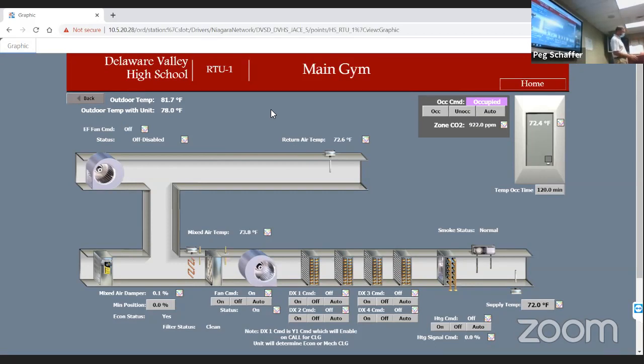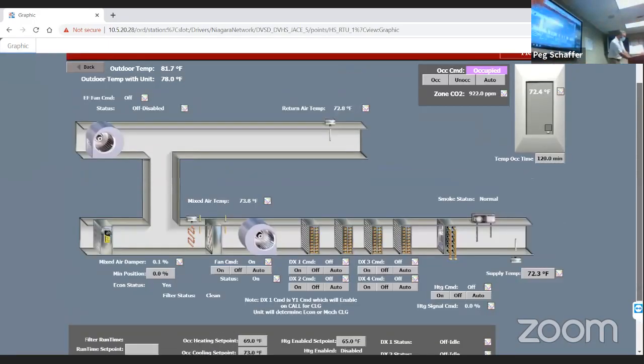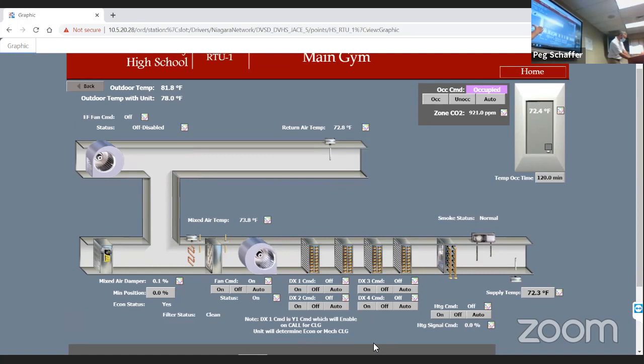So this is a large box you see sitting on top of a roof. That's the ventilation for the main gym. There are two units up there, fairly new, very efficient equipment. One of the things I'd like to point out, Matt, on a graphic like this, again, it's a tool that the school district made an investment in. You can see, you don't have to go to the room to look at the thermostat to see what the temperature is. It's telling you what the mixed air temperature is that's being discharged through the unit.